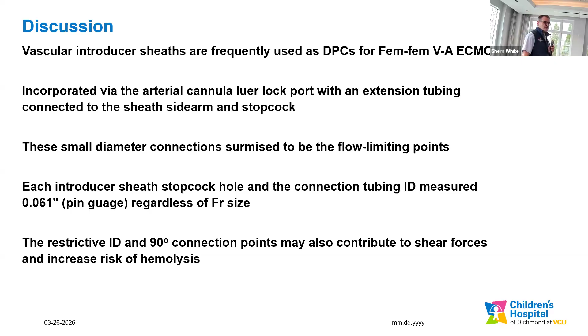What the biomedical engineers found was that each introducer sheath stopcock hole and the connection tubing inner diameter measured 0.061 inches using a pin gauge. Regardless of which French size introducer sheath you use, they were all limited by the little flow ports inside the stopcock and the connection tubing itself. So the restrictive inner diameter and that 90-degree connection point was surmised to also possibly contribute to increased shear forces and increased risk of hemolysis in our ECMO patients.